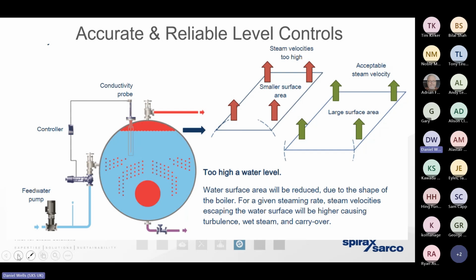And when we know the pressure of the boiler, we've got an understanding of the velocity of steam that is leaving the boiler. Now, if that water level were to rise to a very high point or fall to a very low point, the surface area is going to change. And that means the steam velocity can leave the boiler at a much greater speed than we're expecting. That can drag a lot of water out of the boiler that's really going to contribute to that wet steam that we're desperately trying to avoid. Remember, wet steam means we're going to get a lot of erosion of different ancillaries, but there's also less energy in wet steam. And because wet steam is far more likely to condense out in the pipework, we're going to get a higher condensing load and a further inefficiency.